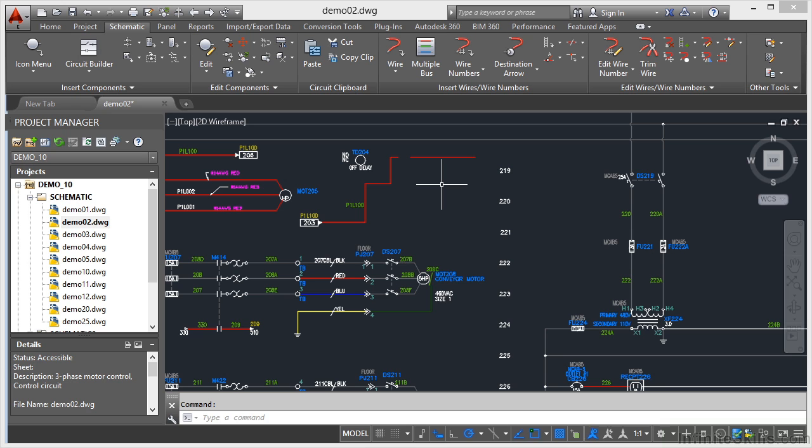So that's how you can show wires in your AutoCAD electrical drawings. That highlighted red because it was on an appropriate wire layer. When it wasn't on an appropriate wire layer, the SYMS layer, it just showed as a white line on that layer, and it stood out. You could see, because it wasn't highlighted in the red, you could see that it wasn't an appropriate wire for the wire network. So use that show wires command to find all of the wires that aren't connected or all of the lines that aren't actually wires in your AutoCAD electrical drawings.